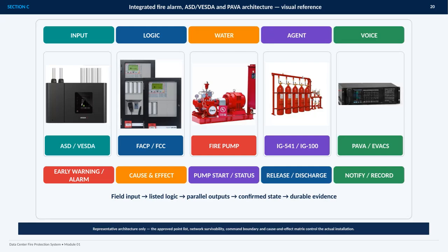This slide provides a visual reference for an integrated data center fire protection architecture. It is organized as a simple flow from field input to durable evidence. At the input level, ASD or VESDA supplies early warning, while the fire alarm control or command center receives and manages the system signals. Those inputs move through listed logic, where the approved cause and effect strategy determines what happens next. The outputs are shown in parallel.